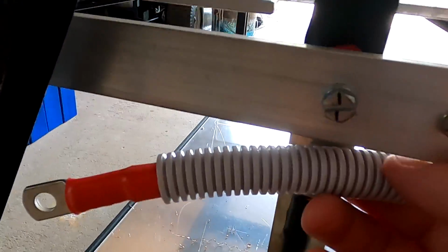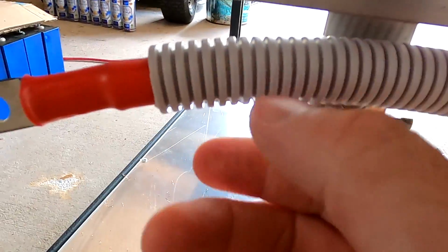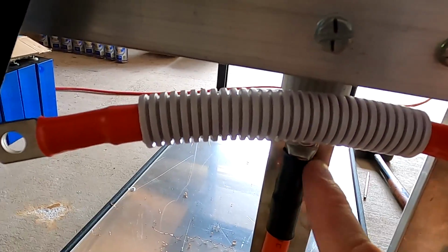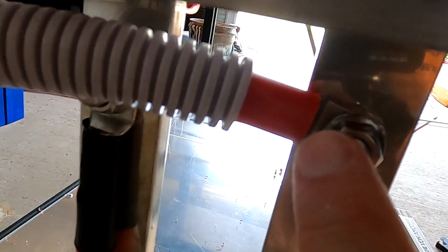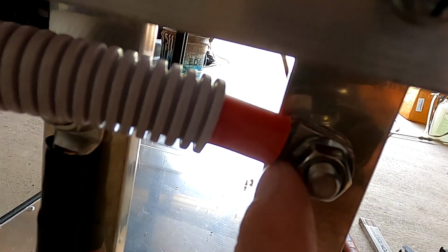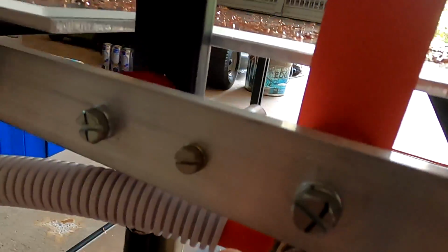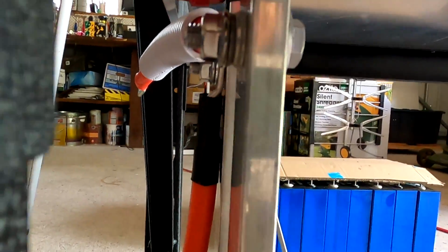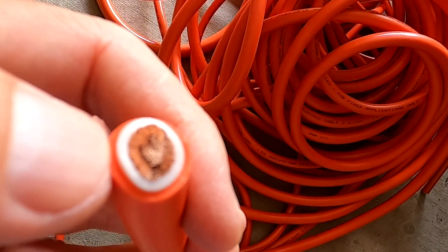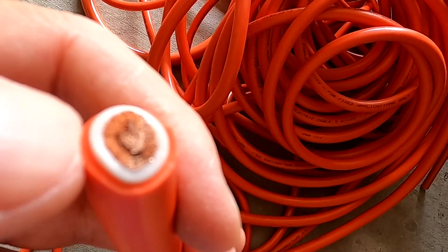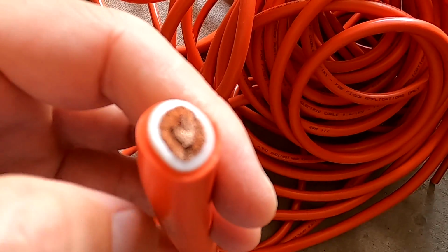You may want to call me paranoid, but I've added this extra conduit over the positive cable because we're crossing the negative cable here. I've bent the ring lug just a tiny bit so it comes a little away from the negative—you can see it angles away. It's not touching the negative bus bar at all, and it will be even more like this later. I like this extra layer of protection: the cable already has nice thick 2-layer insulation, and then we've got the conduit on top, so we'll have around 8-9 millimeters of insulation.